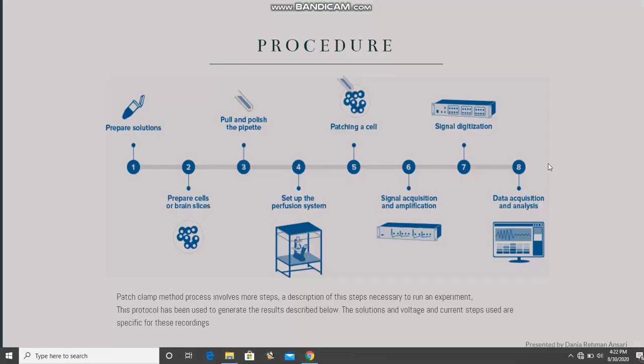The current or voltage signal acquired by the amplifier is an analog signal, but high resolution patch clamp measurement needs data analysis. The analog signal must be converted into a digital one, so position the digitizer between the amplifier and the computer. Signal quality is extremely important and is impacted by the sampling frequency. This whole setup is also equipped with a hum silencer which eliminates the line frequency.